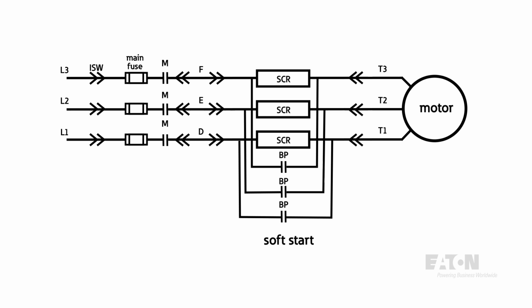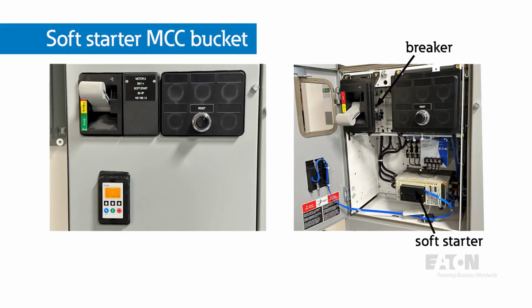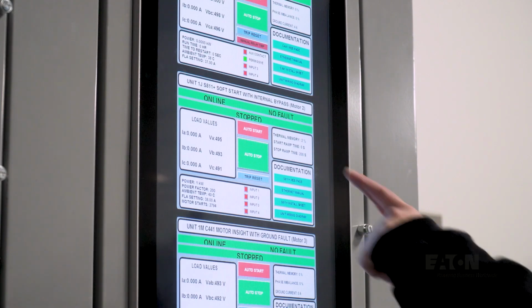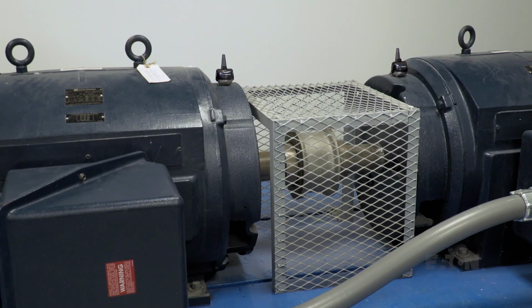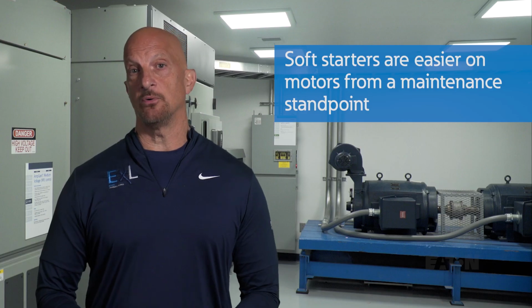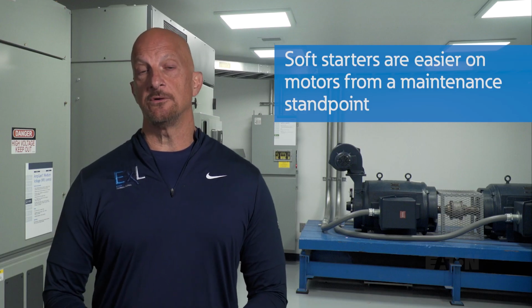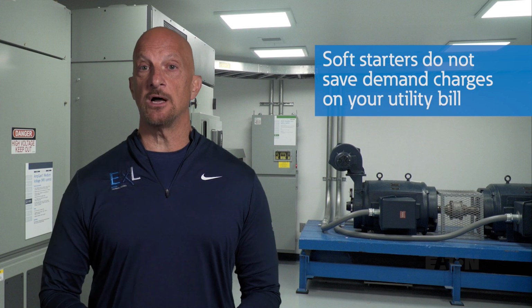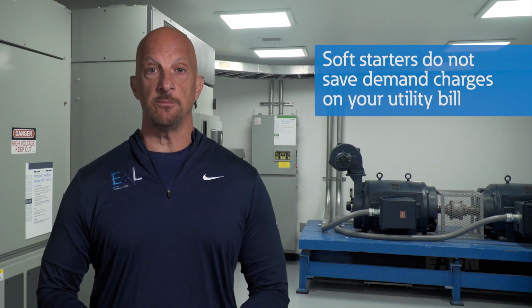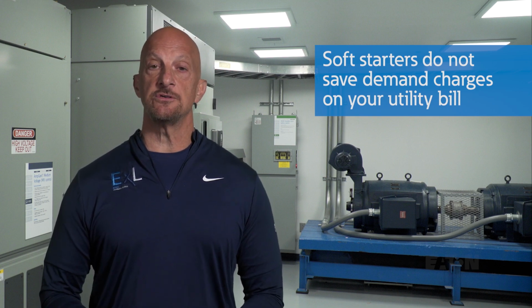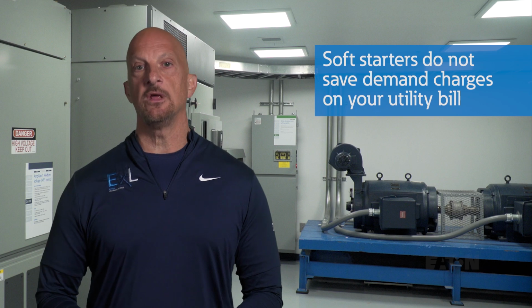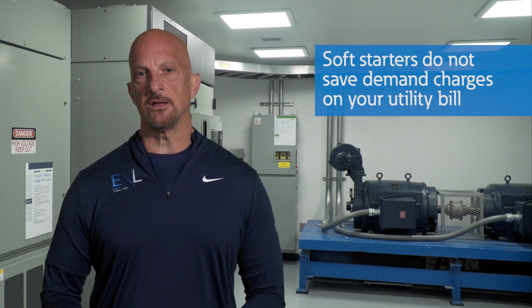Like the ATL starter, the soft starter needs a partnering device to handle fault currents, so it pairs up with a fuse or a breaker. The soft starter is more gentle on the motor and therefore can have a financial benefit over the standard ATL motor starter from a motor maintenance standpoint. One important point to understand is that soft starters do not save demand charges on your utility bill, because those demand charges are averaged over 15 minutes and motor starters only take a few seconds.